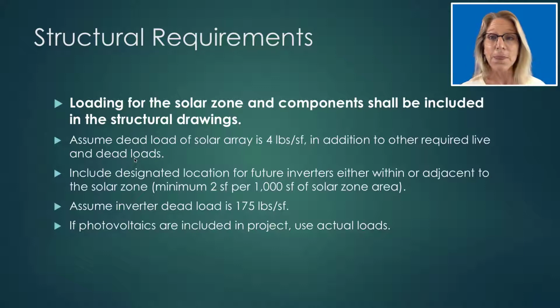So for the structural engineer, they are required to include loading information for the solar array and any components on their structural drawings. So they need to assume a dead load for the solar array of at least 4 pounds per square foot, and that is in addition to other required live and dead loads that would be on that roof area. And then they need to include a designated location for the future inverters, either within or adjacent to the solar zone. And the minimum for that is 2 square feet per 1,000 square feet of solar zone area. And the dead load that needs to be included in their calculations for those inverters is 175 pounds per square foot. And then if photovoltaics are actually included in the project, so this is not just future accommodation, but it's going to be part of that scope of work, then of course the structural engineer would utilize the actual loads and not these minimums.